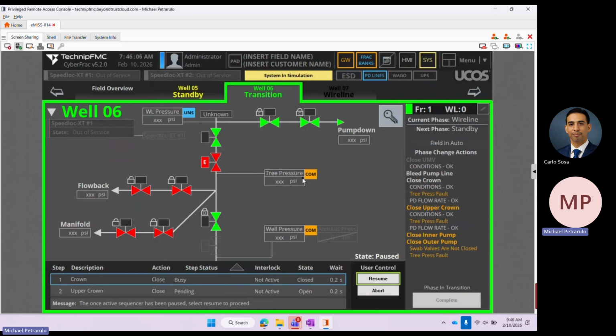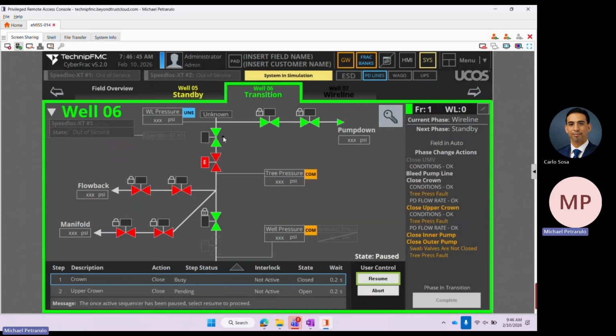Now, normally, if you were to do a regular wireline transition, you have just closed this crown valve. Tree pressure was, say, 4,000 psi. This whole line is still pressurized. In order for me to close the rest of these valves, I have to bleed off that pressure. So pump down is sitting at 4 grand. It's not going to let me close these until this is 0 psi. You'll also notice that I have a C in my lock here, that interlock. As I mentioned, you're allowed to open these pump down wings, but because there's a C, you're not allowed to close them. That's because your upper crown here is still open. Now you have to bleed. Typically you would bleed, you would close this upper crown, and then it'll let you close these pump down wings.